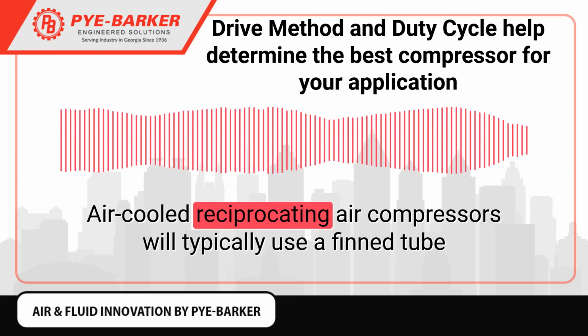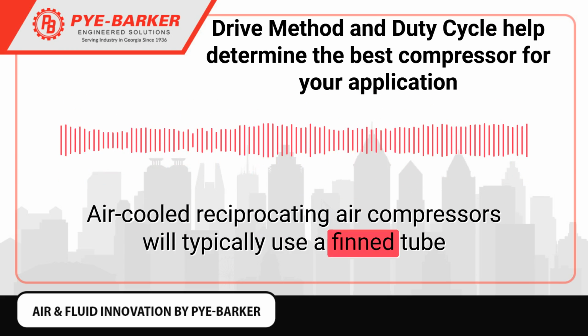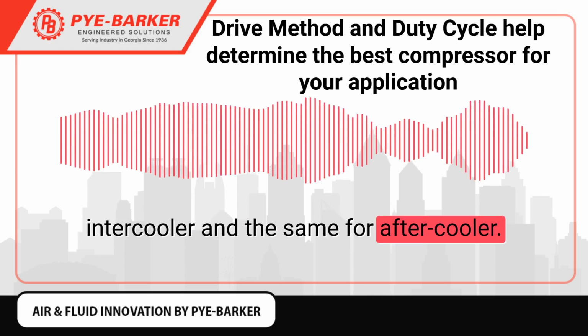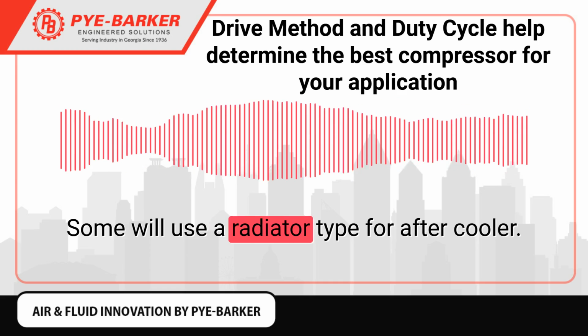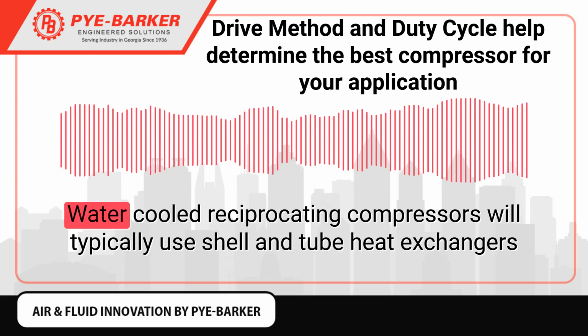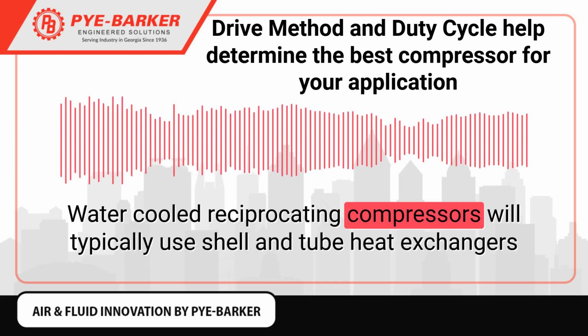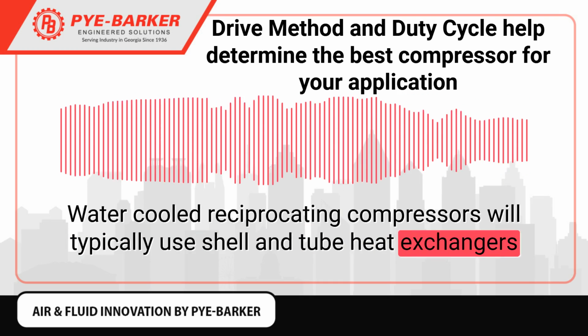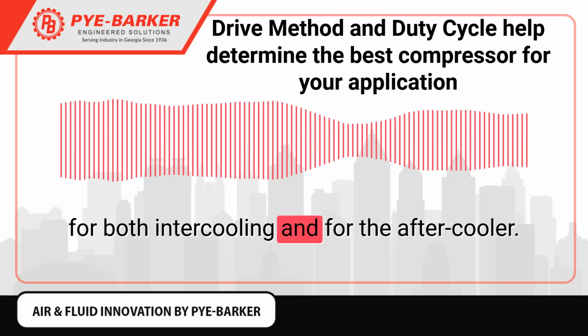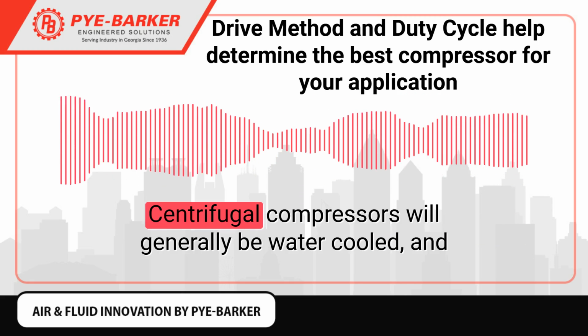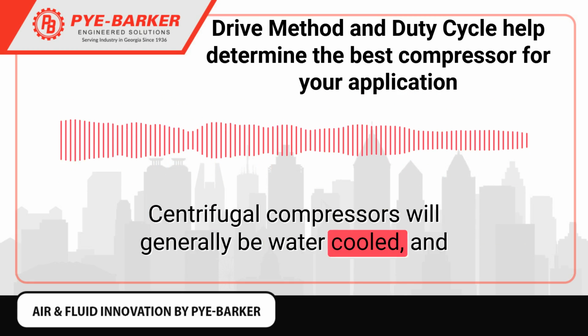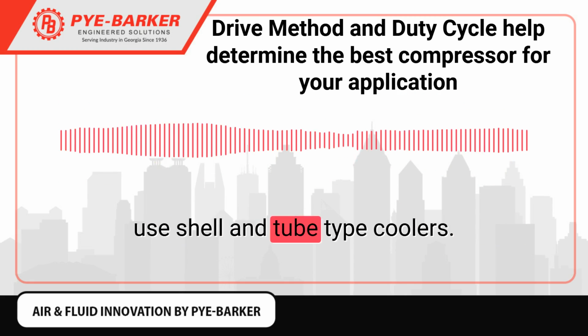Air-cooled reciprocating air compressors will typically use a fin tube intercooler and the same for the aftercooler. Some will use a radiator type for the aftercooler. Water-cooled reciprocating compressors will typically use shell and tube heat exchangers for both intercooling and for the aftercooler. Centrifugal compressors will generally be water-cooled and use shell and tube type coolers.